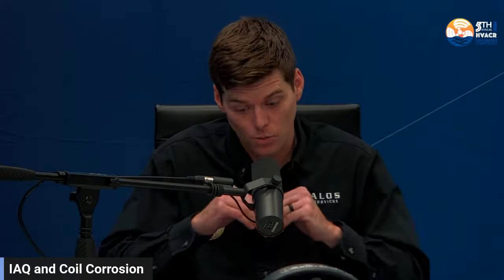You compress it and you expand it, and then you start to create micro cracks. They've even shown that with most coil corrosion that happens inside, it actually acts as a wedge. As it corrodes, the way it pushes itself apart opens up new fresh copper, and then it starts all over again in that same exact process. So creating those wedges, and then heat to cold, you might put it under a lot more stress than it normally would be if it was just straight cool.